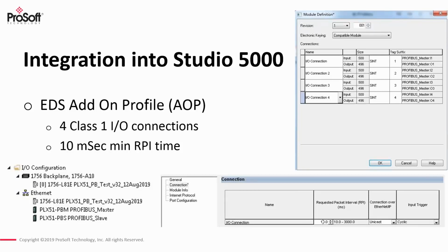And so when we talk about Profibus and Ethernet IP, typically those are two networks that in the past they both require a lot of processing power to be able to keep up with the high-speed update rates. Profibus can run at a baud rate as high as 12 megabits per second, and Ethernet IP with your Class 1 I/O connections in this module, you'll be able to operate at RPI times of 10 milliseconds.